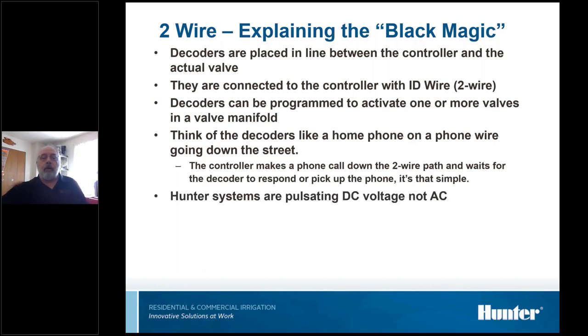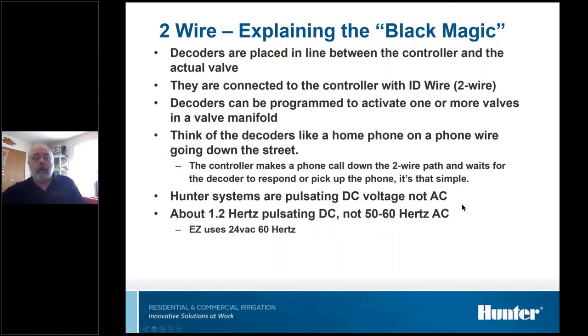One of the things that's different, we use what we call pulsating DC or a square wave signal. It's not AC voltage, and this is part of why the standard test equipment doesn't work so well on decoder systems. Besides being a square wave, it's at 1.2 hertz, whereas normal AC voltage that we're used to is at 60 hertz, 60 times a second. This is only 1.2 times a second of the transition. That 1.2 hertz in the square wave is how we can get tremendous distances out of these systems, how we can go 2 miles on a wire path. The Easy system doesn't. It uses 24 volts AC, and that's why it doesn't have near the distance capabilities.